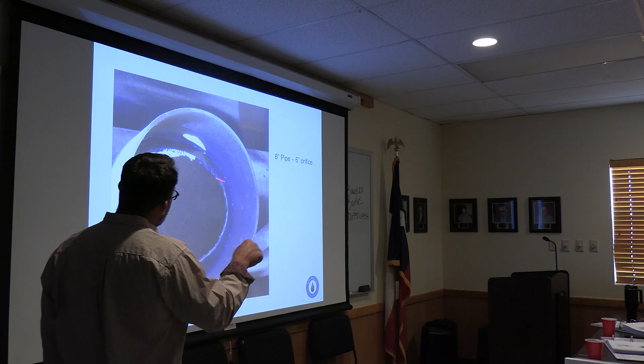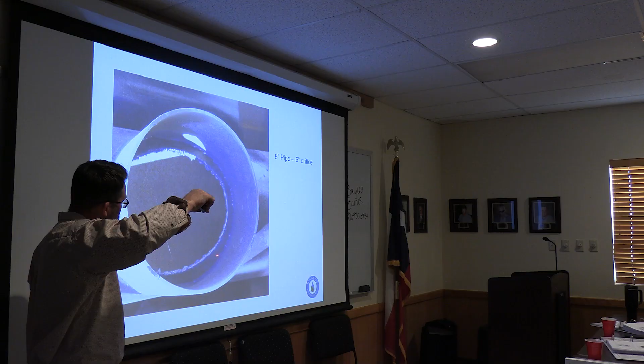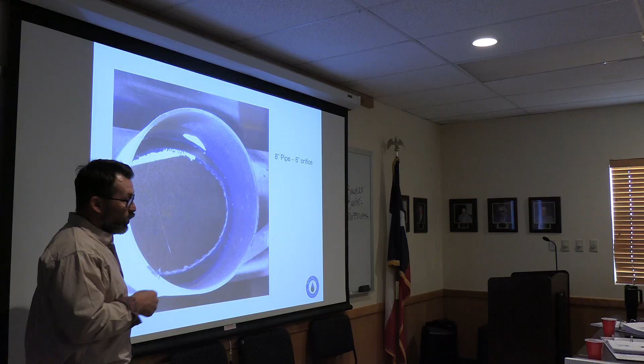Another example would be when you're fitting these pipes. This is a picture actually from this station, this water conservation center, where it's an 8-inch pipe. The builder says, I'm going to build me an 8-inch saddle. We'll see what he did in the middle here. If you're a fabricator, you're like, oh, that's way better. Like, I'm a lot stronger. If you're paying for the energy on that, though, that basically takes it from an 8-inch pipe to a 6-inch orifice, and that comes with a huge pressure loss. In this case, it's a 4 psi loss for every drop of water that flows through that.